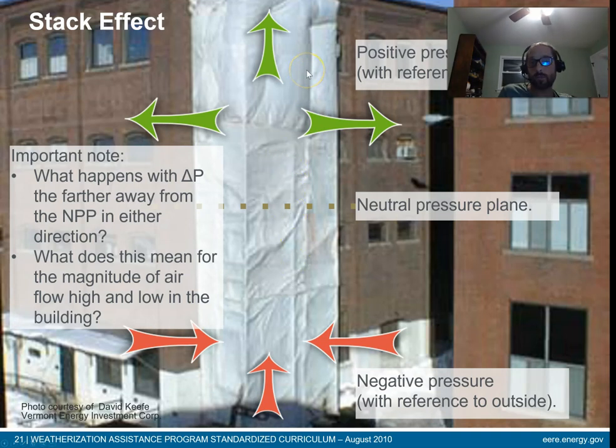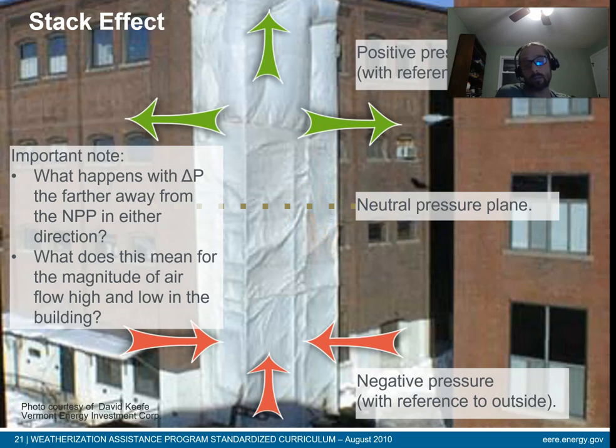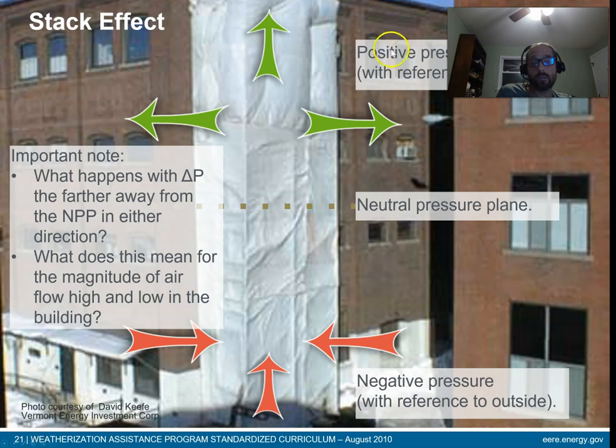The further you get from the neutral pressure plane, the greater the magnitude of the positive pressure up high and the more negative it is down low. Air leaks at the neutral pressure plane will be minor — there's not a big delta P between inside and outside at that point. Up high and down low is where you really get a lot of leakage because of the stack effect.